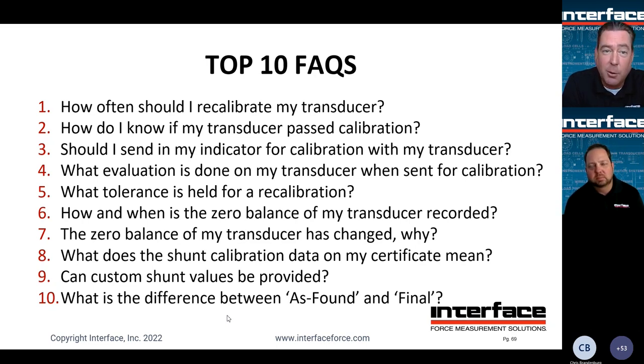That's a highly variable question. If it's a system level cal and the indicator does not have another method of providing traceable calibration at your facility, the answer is always going to be yes. More to the point, it's going to be what calibration are we going to perform at the factory on this indicator set.